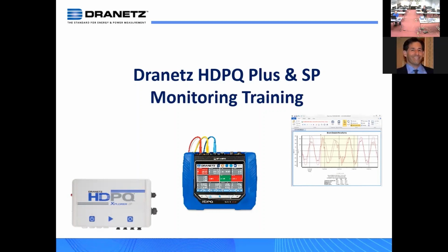They have the exact same communication. On a portable, you may use a touchscreen to set it up and do data analysis, and use the communications, meaning Ethernet or Wi-Fi, if it's available in that model, as a secondary form of user interface. Well, that secondary form on the portable becomes the primary user interface on the SP. But it is the exact same interface, and these are the exact same instruments measurement-wise. So they set up exactly the same. What you see is identical, and what they measure is identical. When you peel back the cover, they are really the same instruments on the inside. So once you know one, you absolutely know the other, given the differences that we spoke about before.